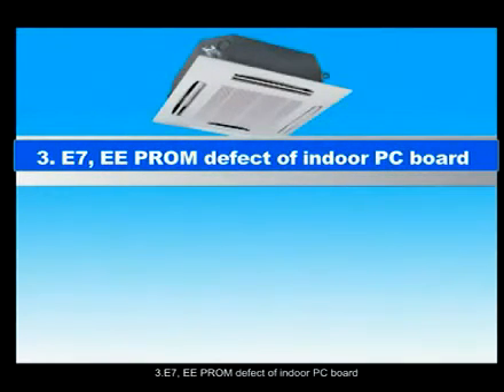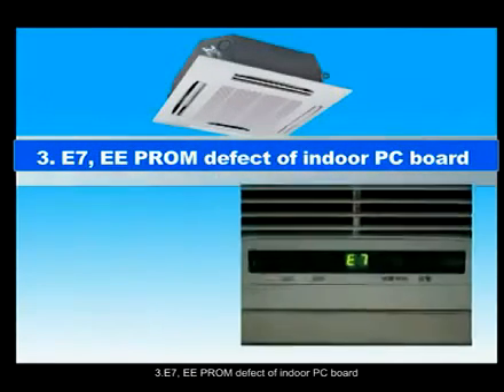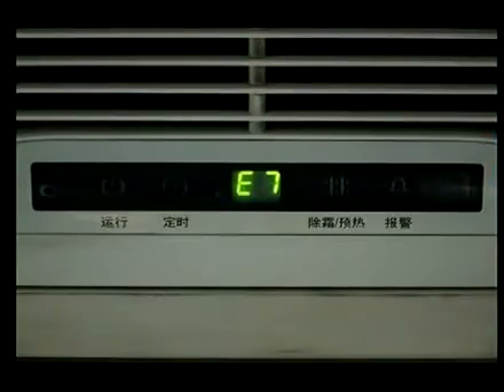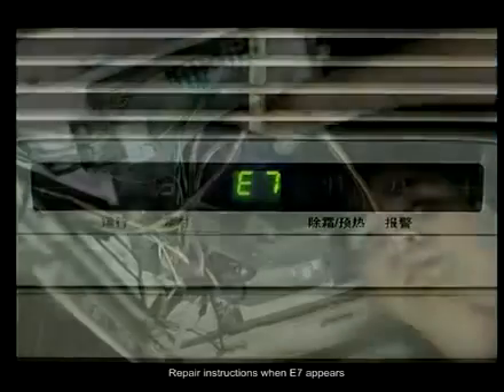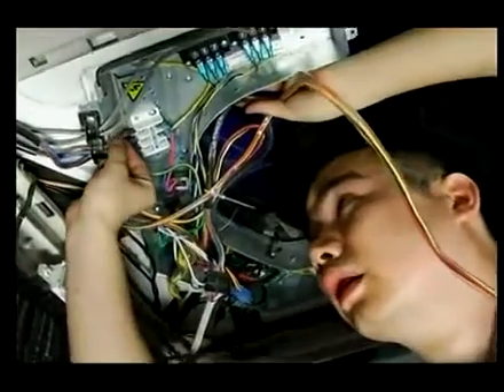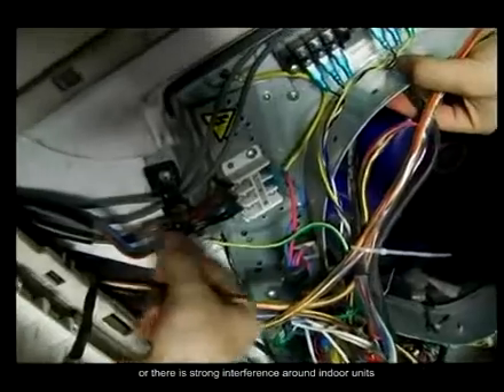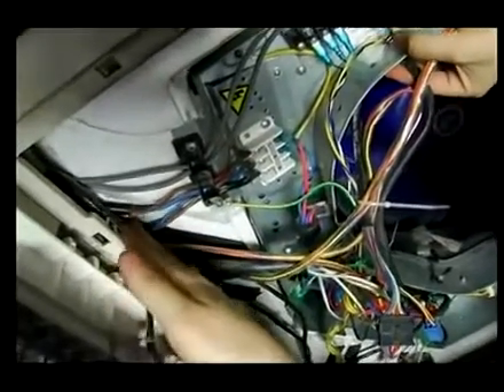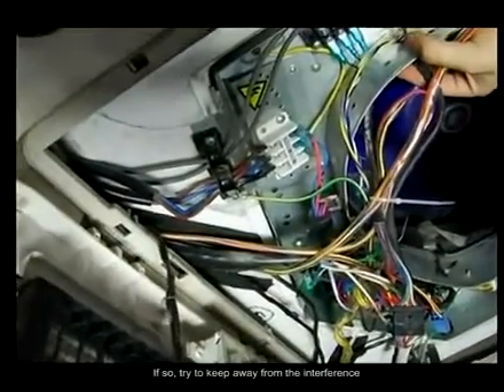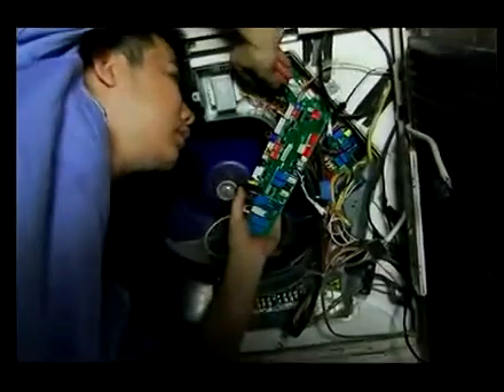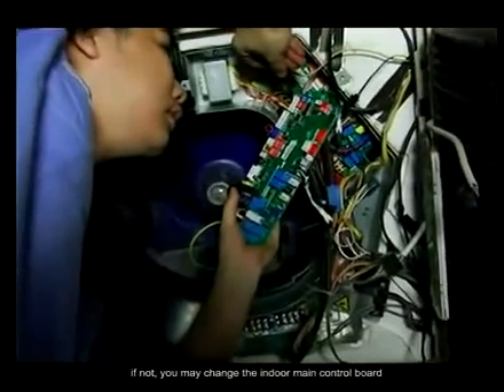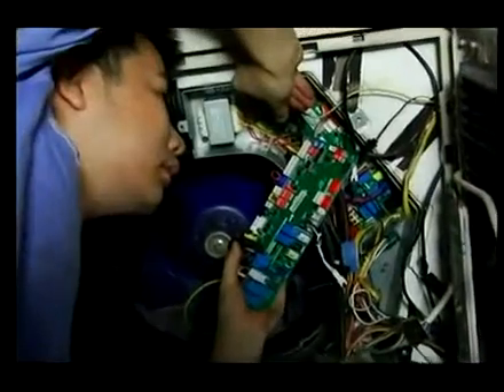3. E7, EEPROM defect of indoor PC board. Repair instructions when E7 appears. Check if the electric control wiring is reliable or there is strong interference around indoor units. If so, try to keep away from the interference. If not, you may change the indoor main control board.